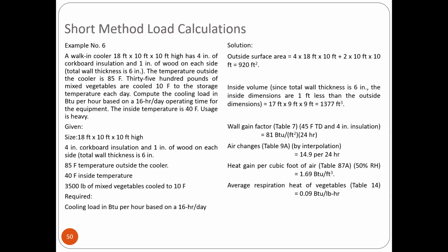is 920 square feet. Inside volume: since the total wall thickness is 6 inches, the inside dimensions are 1 foot less than the outside dimensions. So, 17 feet times 9 feet times 9 feet, so the inside volume is 1377 cubic feet. The wall gain factor from Table 7, at 45 Fahrenheit with 4-inch insulation, is 81 BTU per square foot per 24 hours.